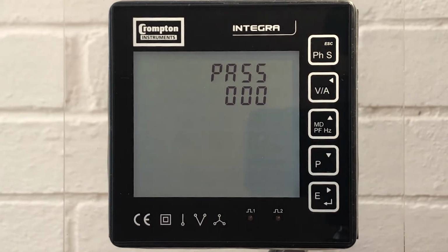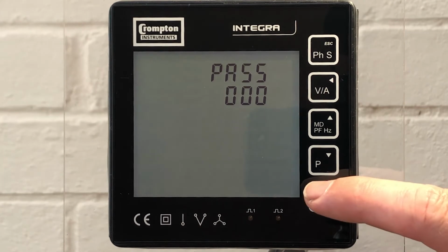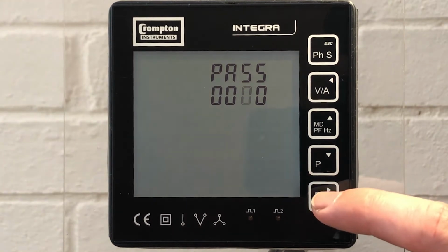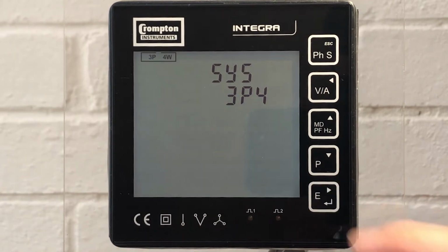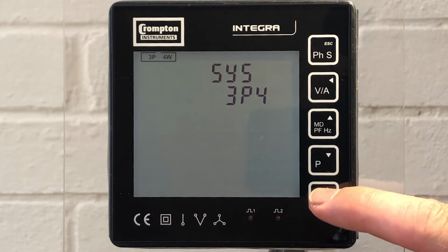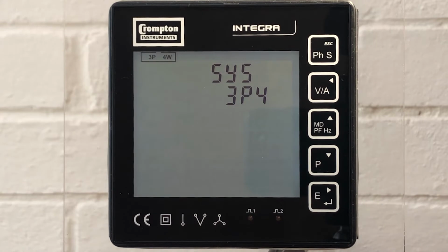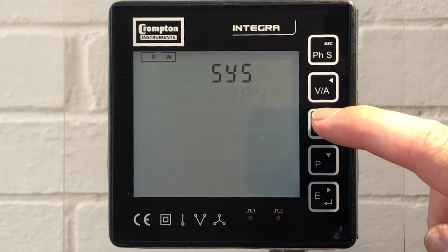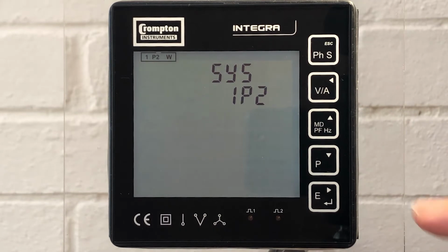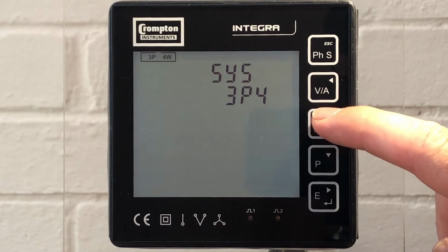To enter the setup menu, press the VA and P buttons together and the Integra will ask for its password. Out of the box, this password is set as 4 zeros. Once into the setup screens, the first thing we can change is the system type. This is the self-powered model, so the available system types are 3-phase 4-wire or 1-phase 2-wire, a single-phase system.